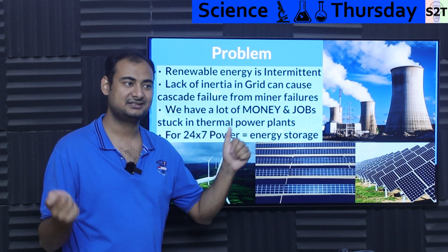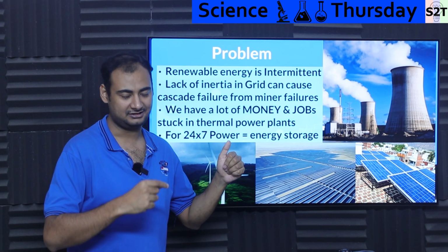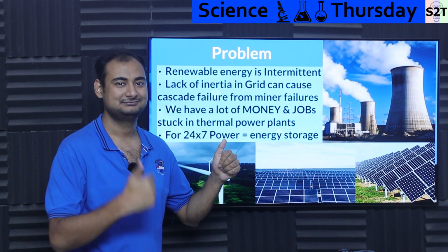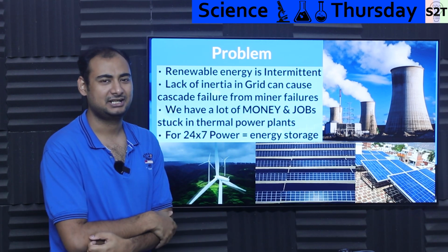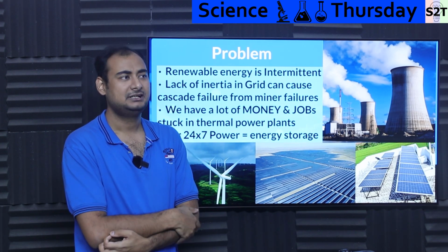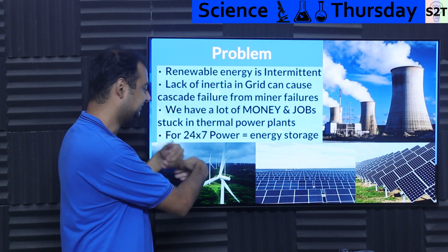There's a small inverter that figures out what the frequency should be, say 50 hertz. If the generator is trying to make 60 hertz, it feeds 10 hertz in counter rotation, so it will slow down. Yeah, it's convoluted, but we had to do that. Now we've just given up on it, yeeted all of that.